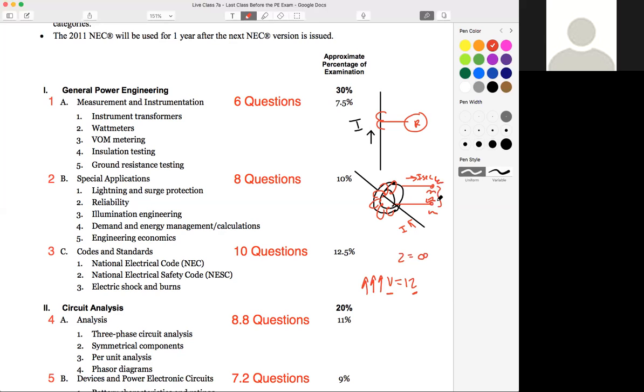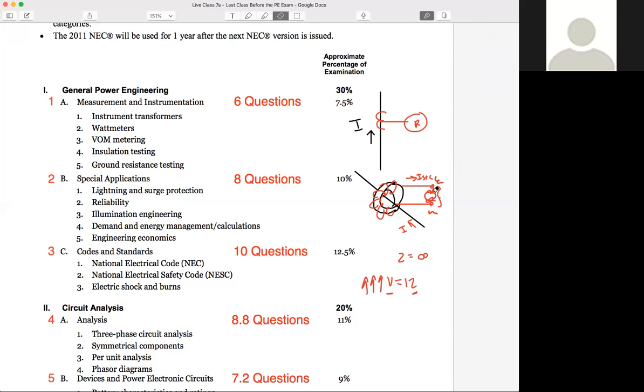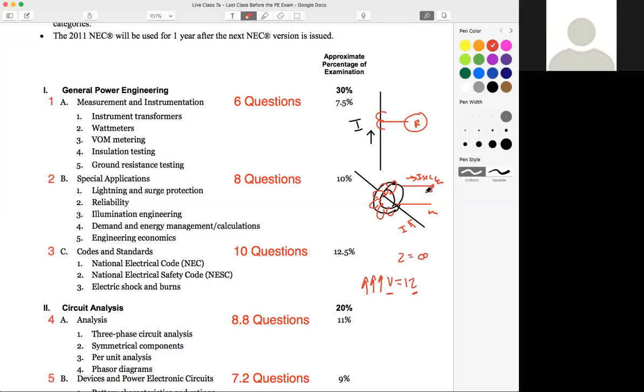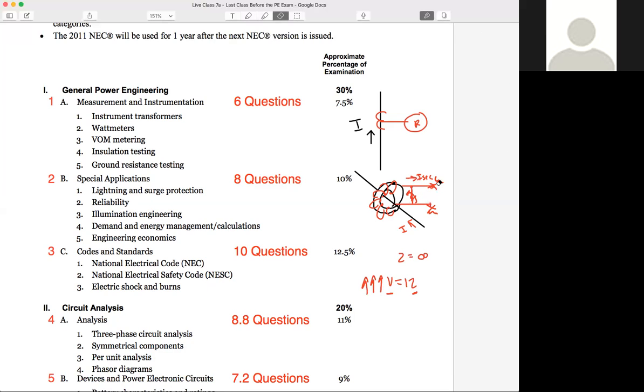It's not fun for those of you that have seen it in real life. That's why they'll say always short the terminal. So example, if our relay was right here like it should be, let's redraw that like this. This is our relay terminals. A lot of times there's like a test switch, or you can use a jumper. And before, say this relay went bad and we had to change out that relay with a new one, before we could disconnect our terminals on our relay, we would have to close this test switch and effectively short our CT. And then we can go ahead and we can remove that relay. And guess what? Even though we've got an open on this side, all of our current is still flowing through that short, that jumper.